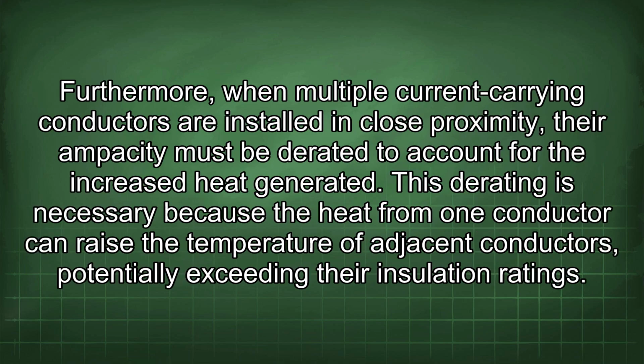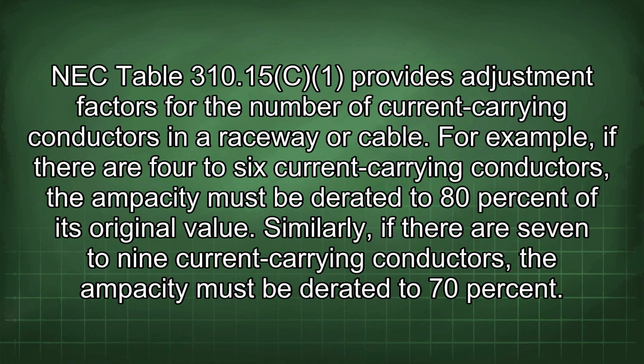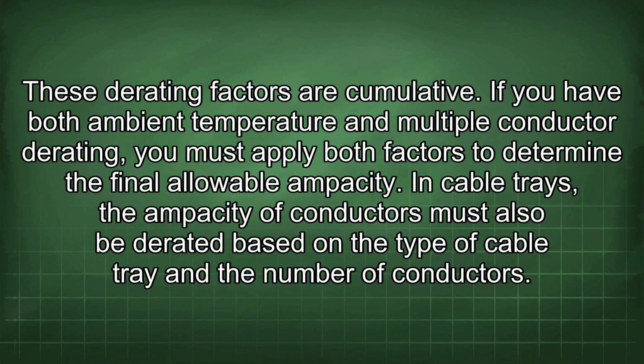Furthermore, when multiple current-carrying conductors are installed in close proximity, their ampacity must be derated to account for the increased heat generated. This derating is necessary because the heat from one conductor can raise the temperature of adjacent conductors, potentially exceeding their insulation ratings. NEC Table 310.15(B)(3)(a) provides adjustment factors for the number of current-carrying conductors in a raceway or cable. For example, if there are 4 to 6 current-carrying conductors, the ampacity must be derated to 80% of its original value. Similarly, if there are 7 to 9 current-carrying conductors, the ampacity must be derated to 70%. These derating factors are cumulative.